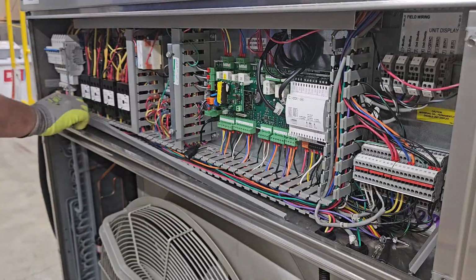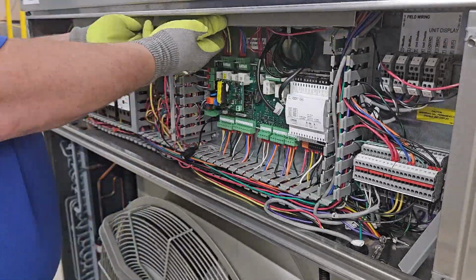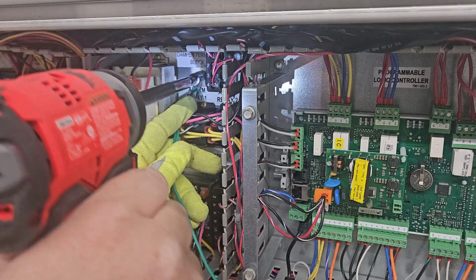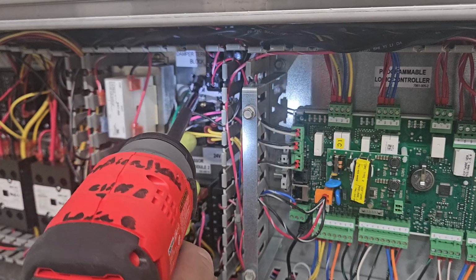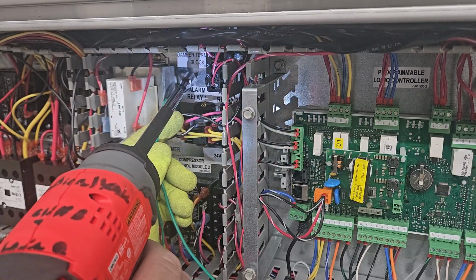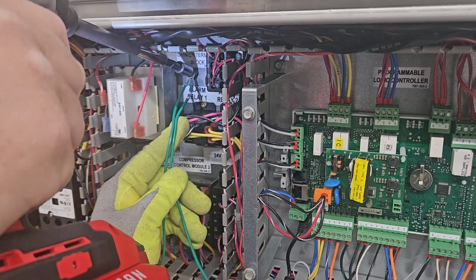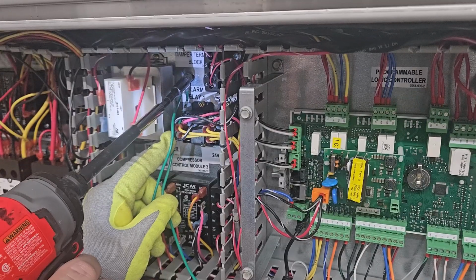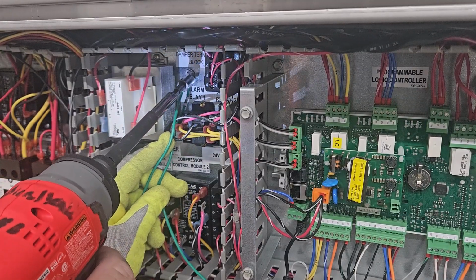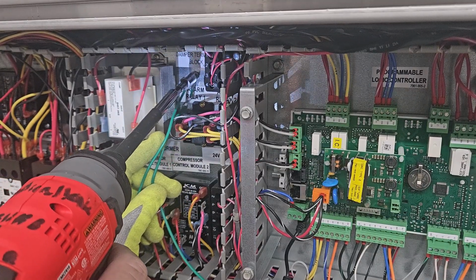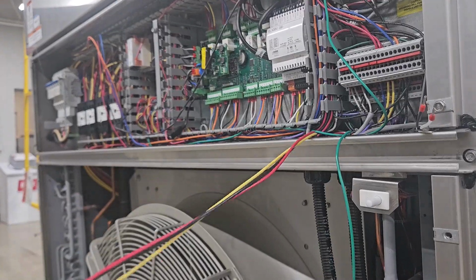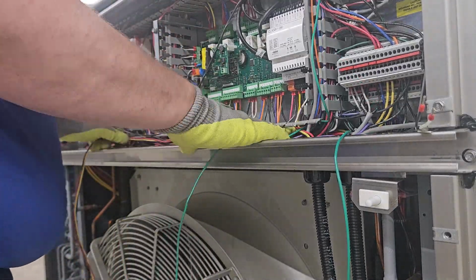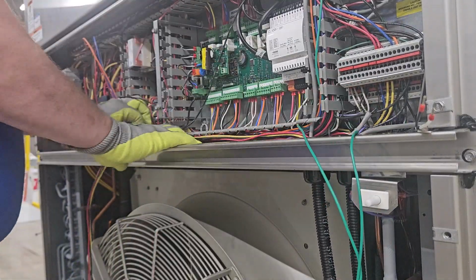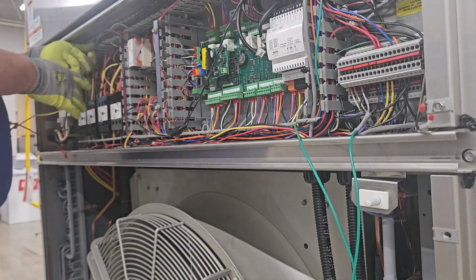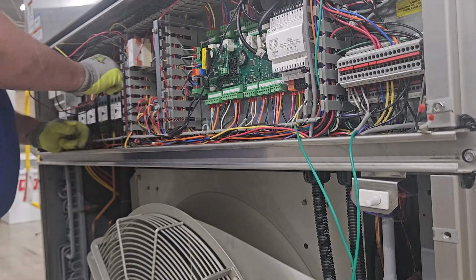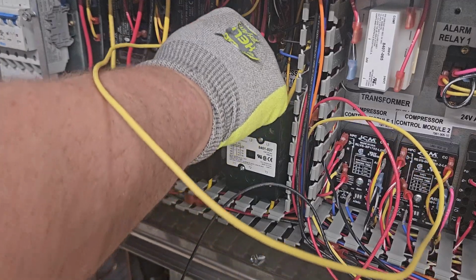Remove the wire chase covers so that we can route the wires to the appropriate spots. Fish the grounding wire, if not already installed, to the screw that is beside the transformer. This grounding area also has the ground wire for the indoor fan motor. Fish the high voltage wires through the wire chase to the third contactor from the left. This contactor is where we'll land the high voltage wires on the line side of the contactor.